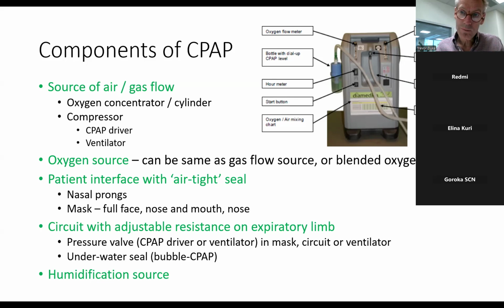And the last thing any CPAP machine needs is a source of humidification. When you're using low flow oxygen, you don't need humidification because of the amount of air that the child entrains in the rest of their breathing; the oxygen goes through the nasal passages, and that humidifies the air well. Humidification is adding water, and that's what our nasal passages do all the time to the air we're breathing in. But if you're giving higher flow oxygen or an air oxygen mix, then you'll get very dry nasal secretions, and sometimes that can lead to nasal or mucosal erosion, some bleeding or ulceration of the nose, or just lead to the nasal secretions getting really thick and blocked up, and the child will have worse respiratory distress. So a humidification source is very important.